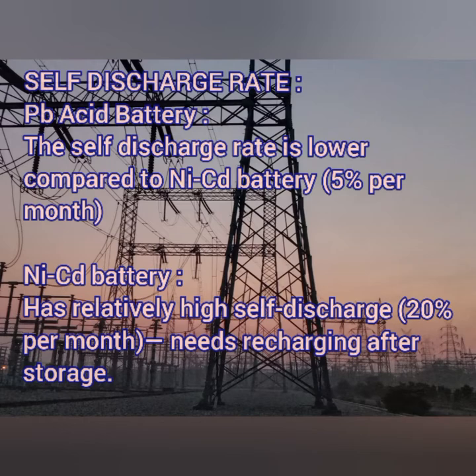Next is self-discharge rate. Lead acid batteries have a very low self-discharge rate of about 5 percent per month, which can be managed by trickle charging. When storing a lead acid battery, you need to fully charge it, remove the electrolytic solution, and keep it as a dry cell.